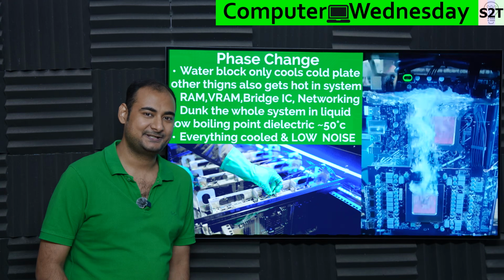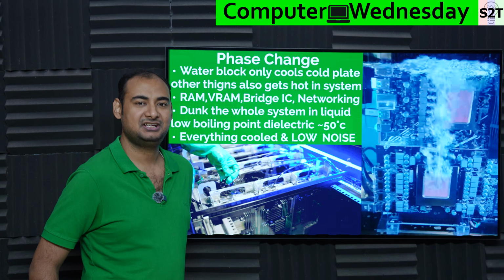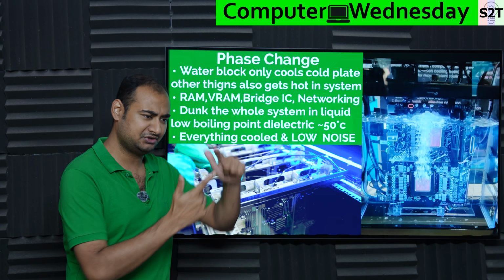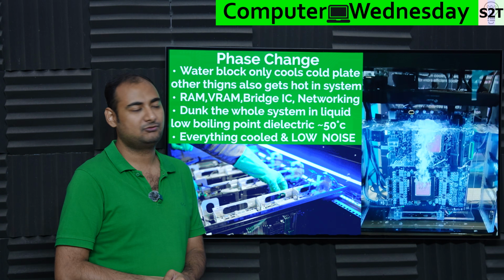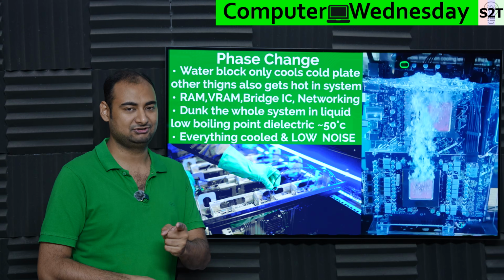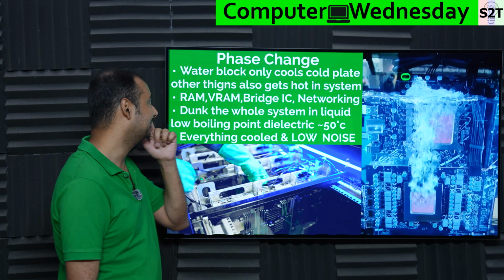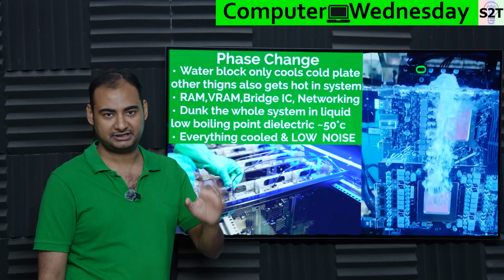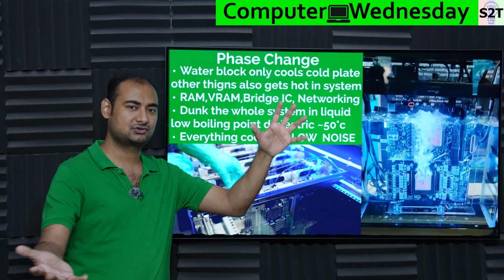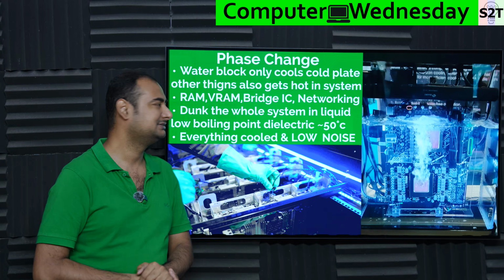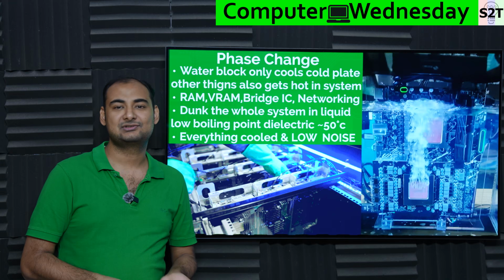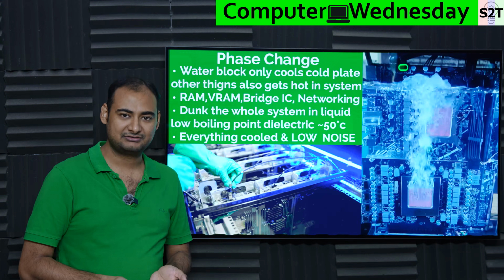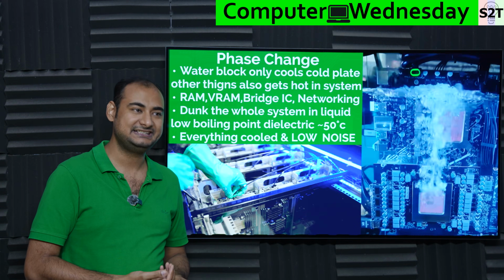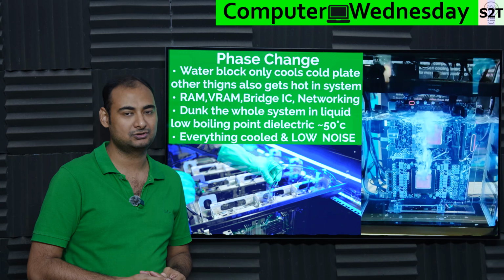That milestone has been crossed, because somebody is pushing things so hard they're asking, what if we put 100 kilowatts in one server rack? Water cannot do that, not because water itself can't, but because your computer can't handle it. For example, water blocks are the cool unit, you put it on your GPU, GPU is cold, everything's awesome, but what about the things around it? Fundamentally, other things also get hot. If you're dumping that much energy, even 1% waste heat is bad enough that over time it will cook other components, for example the worst case would be VRMs.